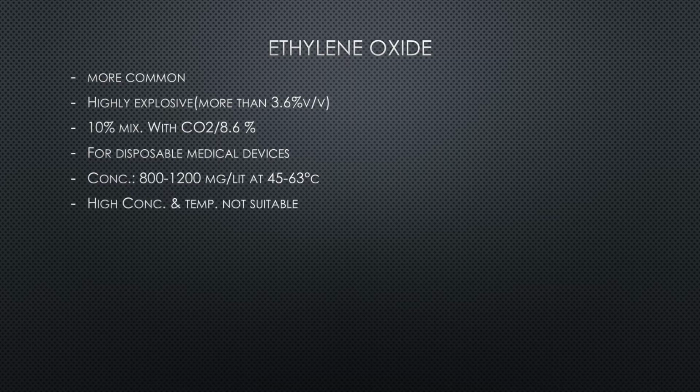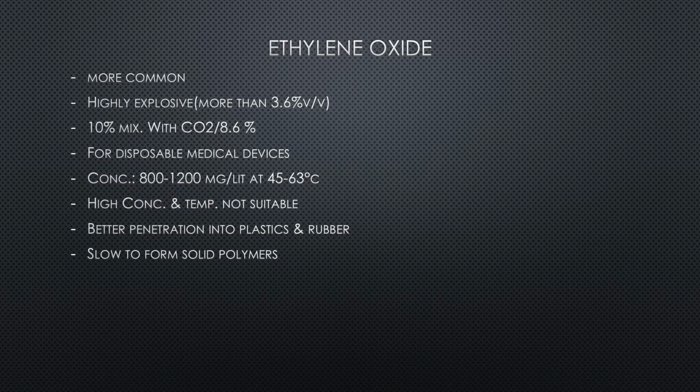This is assisted by the better penetration power of the gas, which diffuses readily into many packaging materials including rubber, plastic, fabric and paper. During the process, the treated article must undergo a desorption stage to remove the toxic residues. Desorption time ranges from 2 to 24 hours.